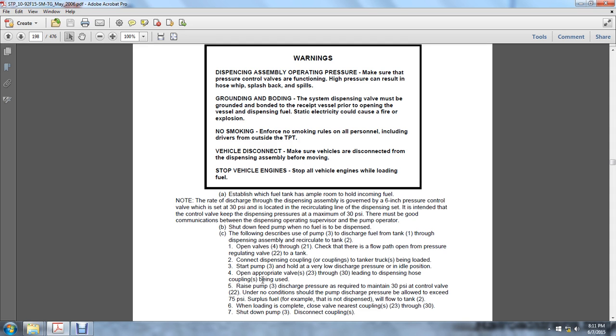The fueling procedure describes the use of pump 3 to discharge fuel from tank 1 through the dispensing assemblies, recirculated to tank 2. Open valves 4 through 21. Check that there is a flow path open from the pressure regulating valve 22 to the tank. Connect the dispensing couplings to the tanker trucks being loaded. Start the pump and hold a very low discharge pressure at idle. Open the appropriate valves 23 through 30, leading to the dispensing hose coupling being used.